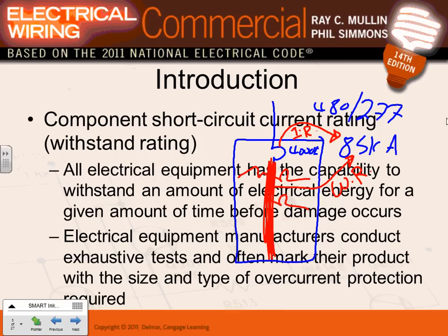And these two values, guys, can decide the thermal and the magnetic energy that this equipment can handle. Thermal and magnetic energy. This is where UL becomes a big deal. That's where UL says, okay, Jeff, this is your switchgear, and you pretend that your switchgear can handle 85. Yep, we're gonna go inject 85,000 amps, right?